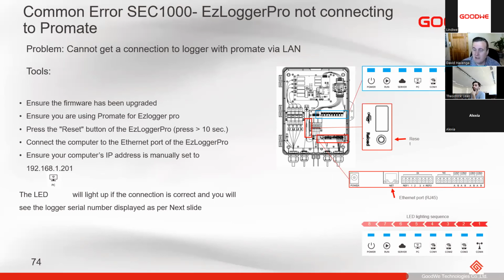Then we have to set the logger to a static mode. So on the side, we have a Reset button. So you press and hold this Reset button. You hold it for approximately 10 seconds. When you let go, you'll see the LEDs will cycle from right to left, as you'll see here. So each LED will go on 1, 2, 3, 4, 5.